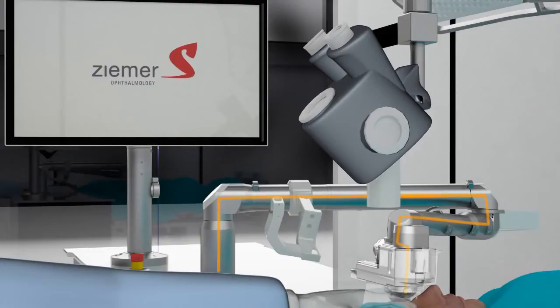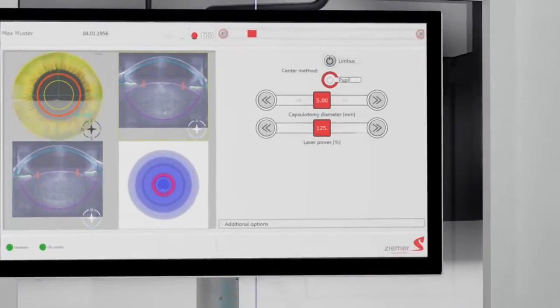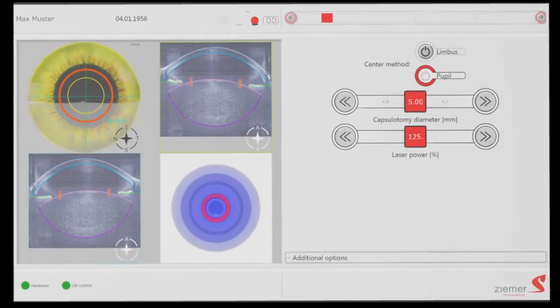An OCT image for intraoperative surgery planning is then taken. The OCT system is integrated directly into the handpiece and, using the same optics, provides precise alignment with the laser for an accurate capsulotomy.